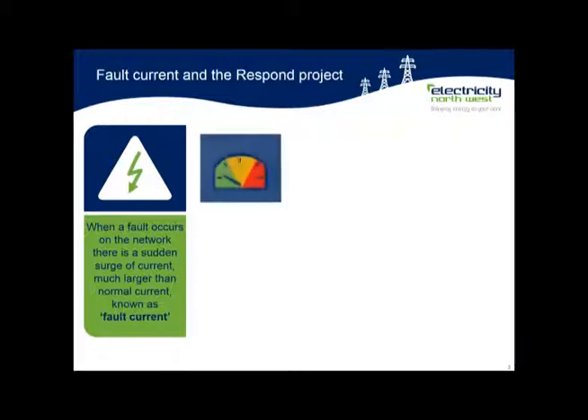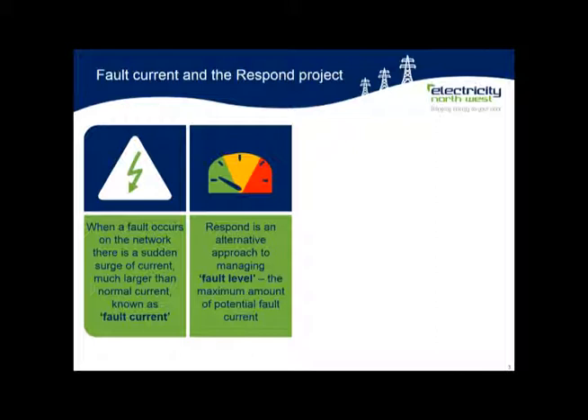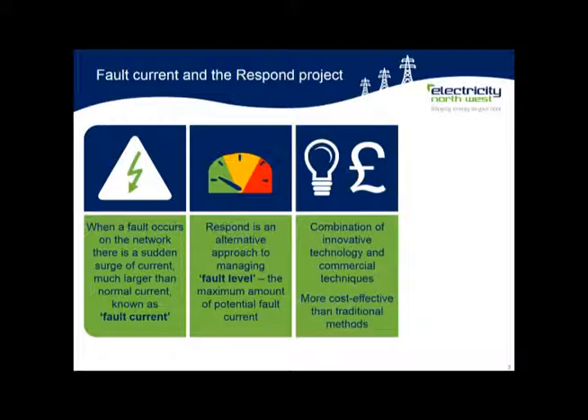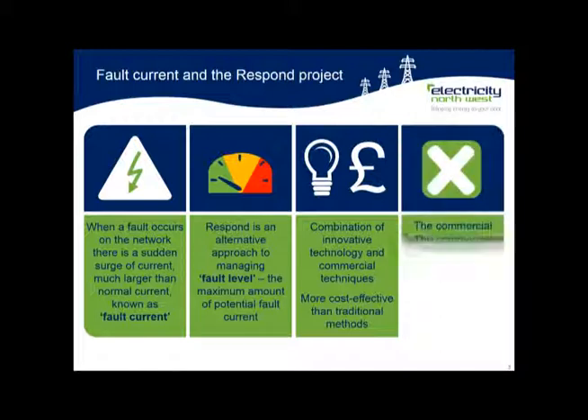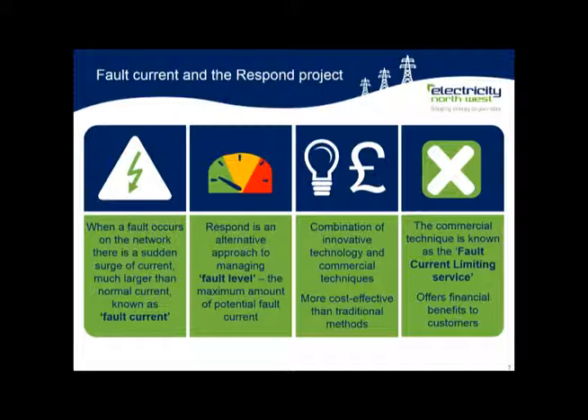The Respond project provides an alternative approach to managing fault level, which is the maximum amount of fault current that can flow. Respond uses a combination of innovative new technology and commercial techniques to achieve this, which is more cost effective than our traditional replacement approach. The commercial technique offers financial benefits to customers taking part and is known as the fault current limiting service.